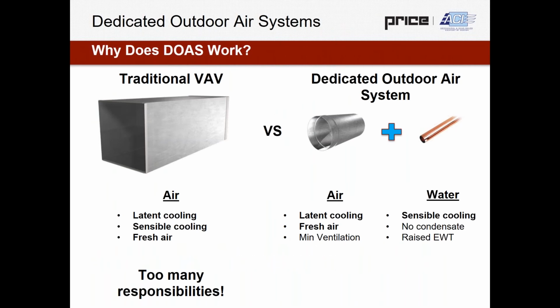As a bit of an intro, a very quick review: why does DOAS actually work? It really comes down to the fact that in comparison to traditional VAV, which puts all of the responsibilities of the system into air only, latent cooling, sensible cooling, and ventilation, DOAS decouples the responsibilities between air and water, and that leads to a more efficient system overall. We have latent and fresh air being handled by primary, and we have water handling sensible cooling only. The biggest reason this works so well is that decoupling, which means both sides can be balanced and selected more efficiently.